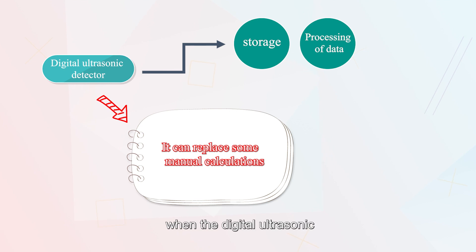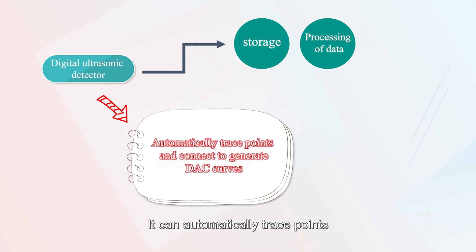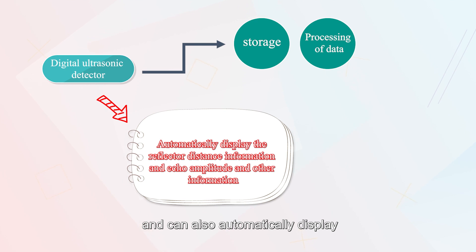For example, when the digital ultrasonic detector is used for testing, it can automatically record the probe parameters such as the k-value of the angle probe. It can automatically trace points and connect them to generate DAC curves and can also automatically display the distance information, echo amplitude, and other information of the reflector.